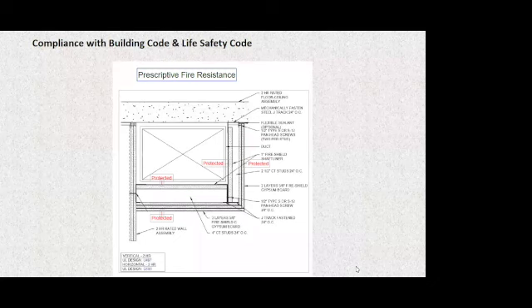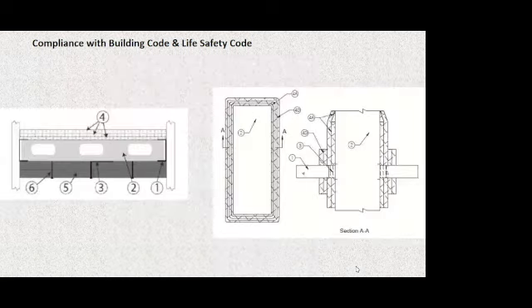I can't stress enough here. These are all life safety applications. All of these systems need to work to protect the property, to protect the occupants. If we don't give the first responders the chance that they're expected to have to do their structural firefighting through protected means of access to the building, we are fundamentally failing. And anything less than what is fire rated by testing, by design, is just wrapping paper made to look like it's fire rated.